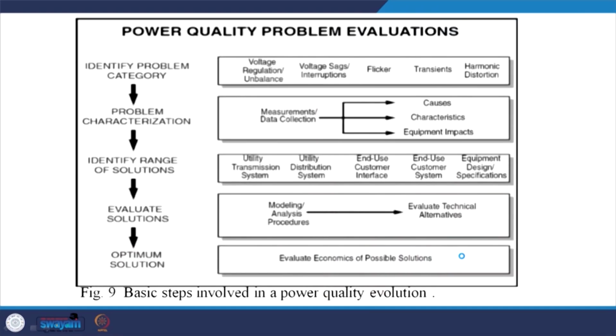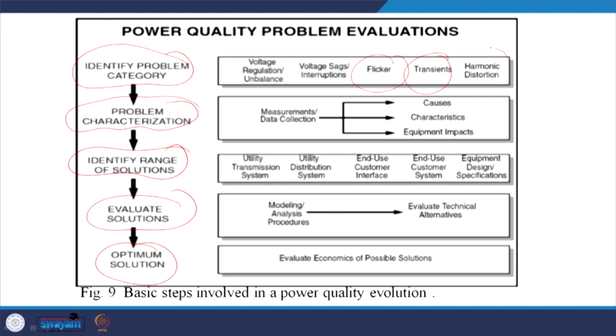So, look, this is a power quality problem evaluation chart. You have to identify the problem category. Thereafter, we have to do a problem characterization. If it is a striking short term phenomenon, it is a voltage sag. So, you have to categorize it. Then identify the range of solutions, then evaluate solutions and find the optimal solution. This is the way you will proceed. For example, voltage regulation, unbalance, voltage sag, flicker, transient, harmonic distortion or THD. These come under this entity.